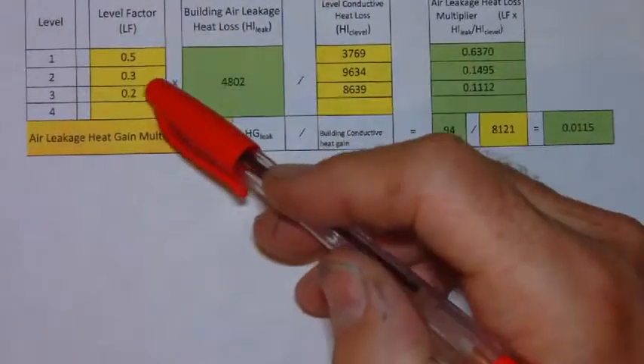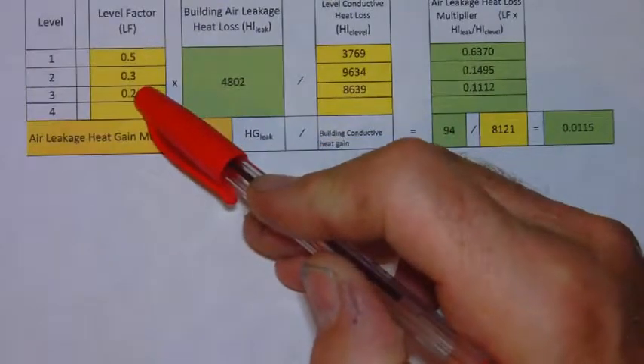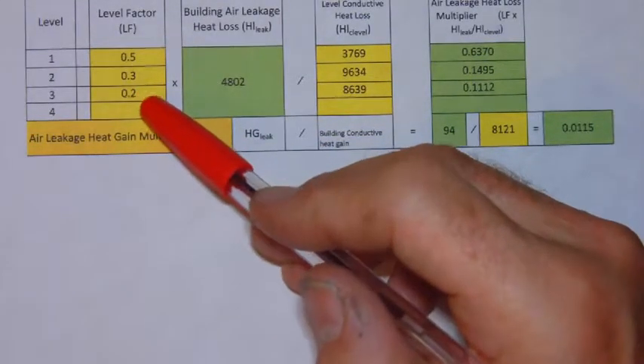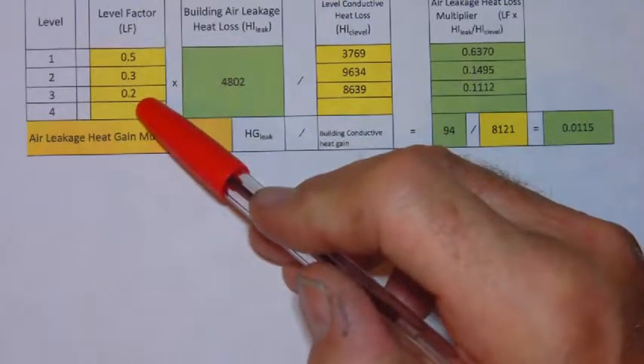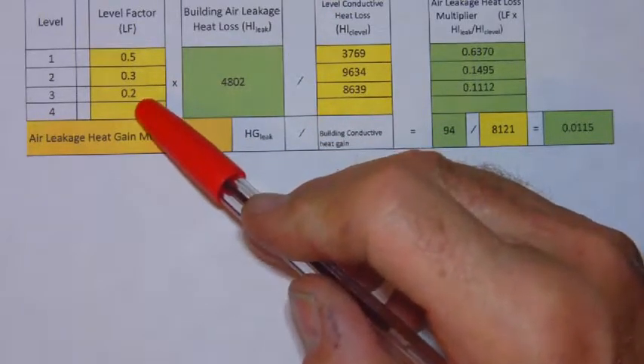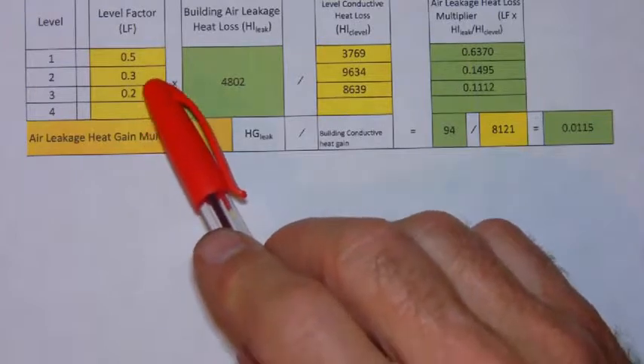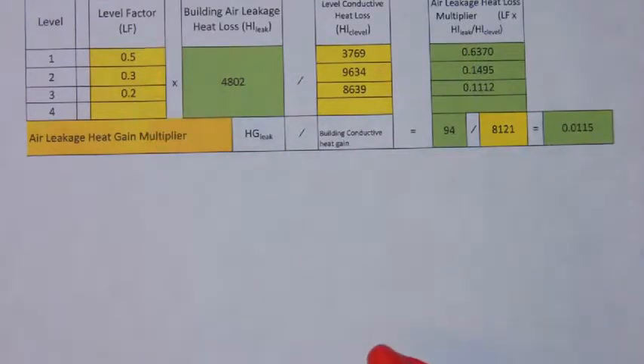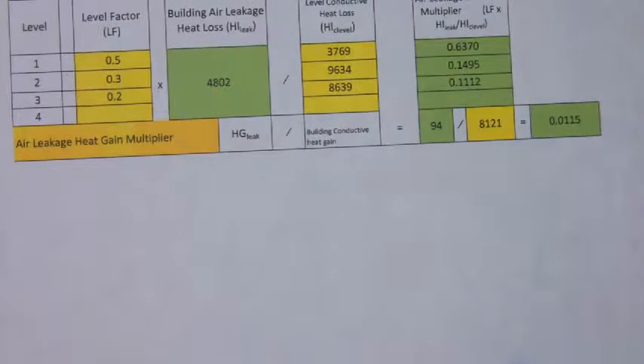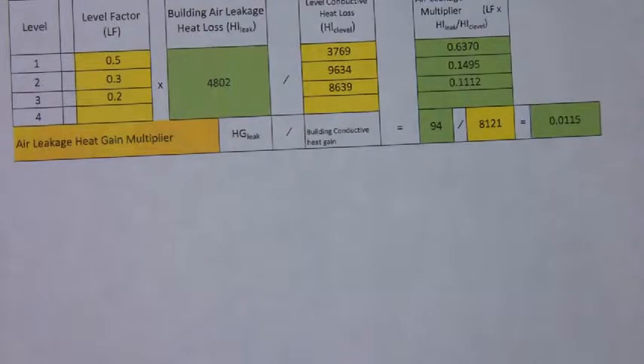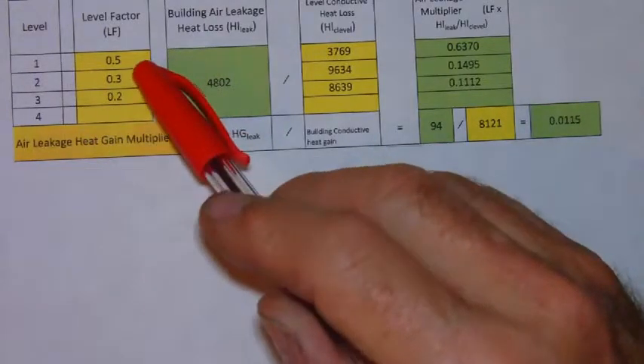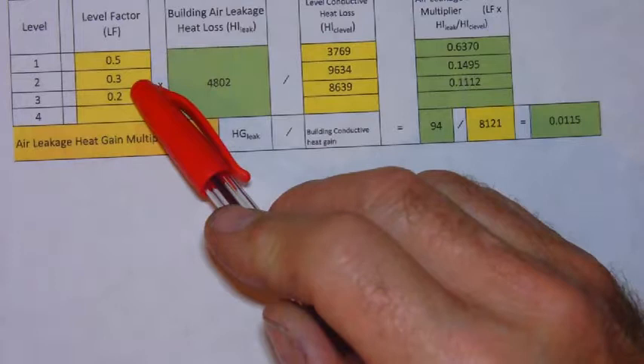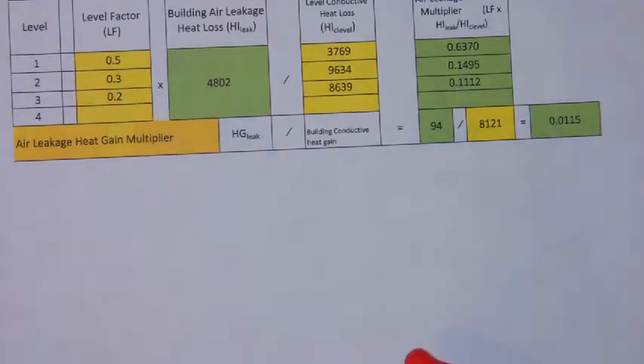Then you need to go to your heat loss manual and I believe it is table nine and you will find the level factors appropriate for a three level house that's a basement with two floors above. In this case you're going to have 0.5 for the level one, 0.3 for level two and 0.2 for level three.